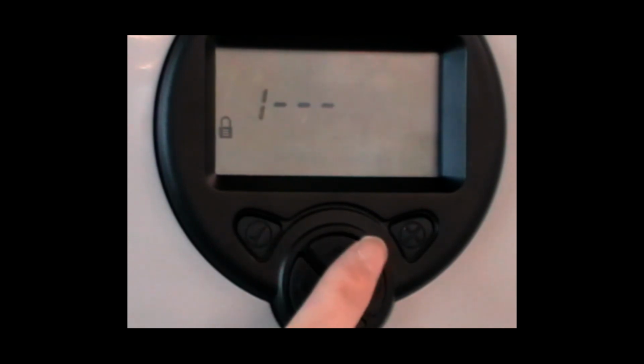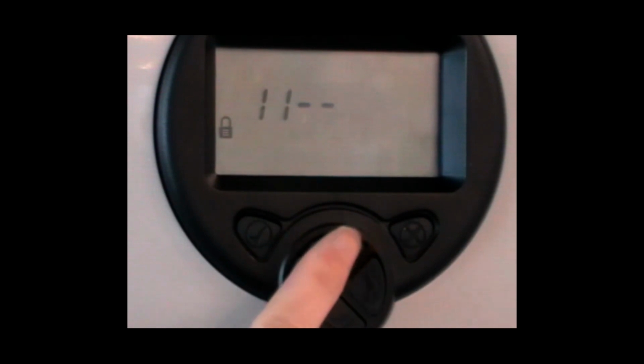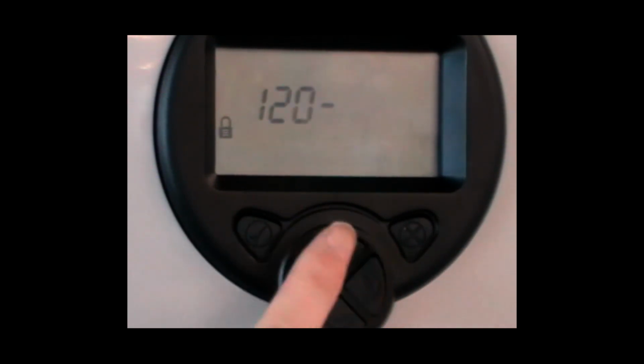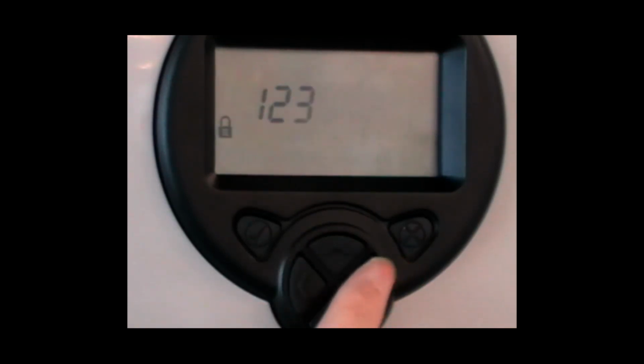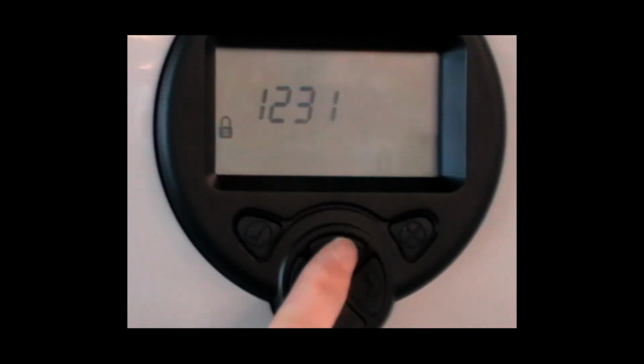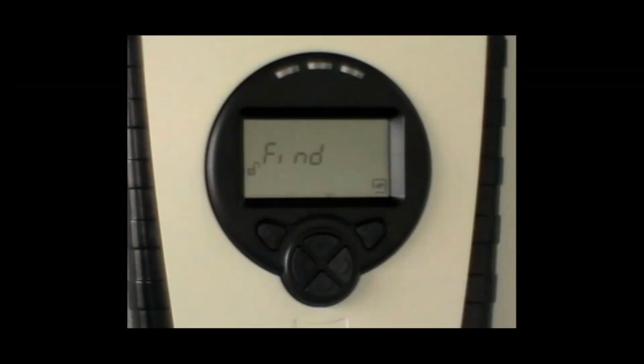Enter the passcode using the keypad. Default is 1, 2, 3, 4. This takes you to the engineering menu. For a system that's not yet set up, the command find will be displayed. Press the tick button to start the find command.